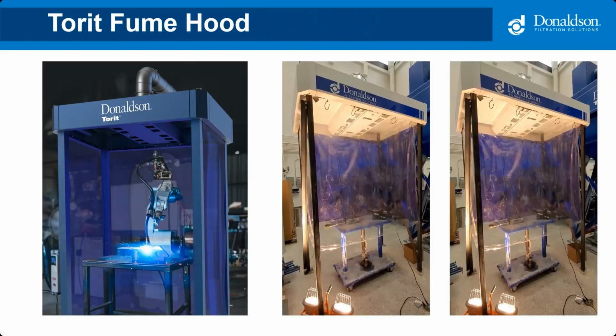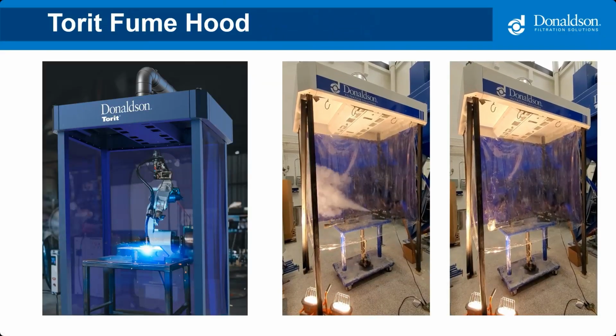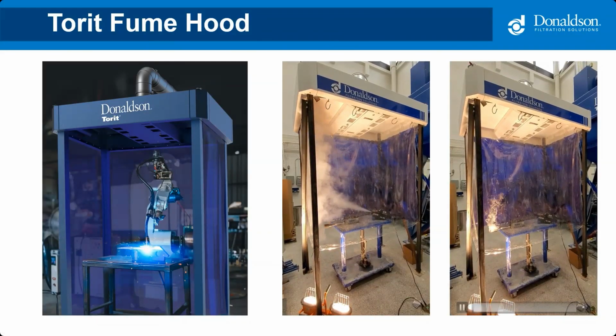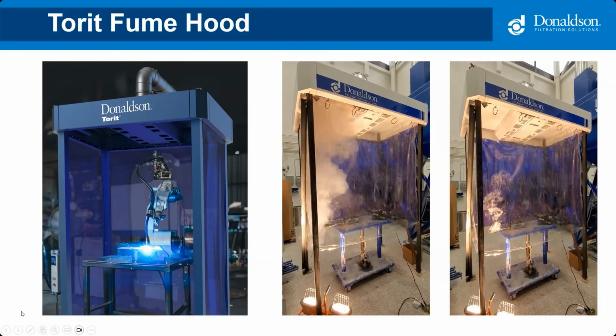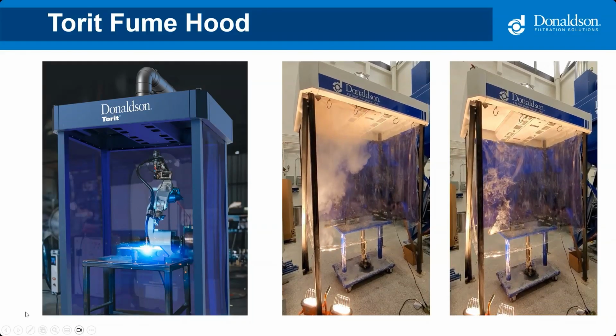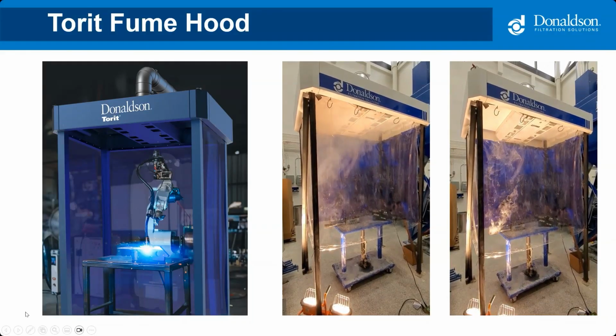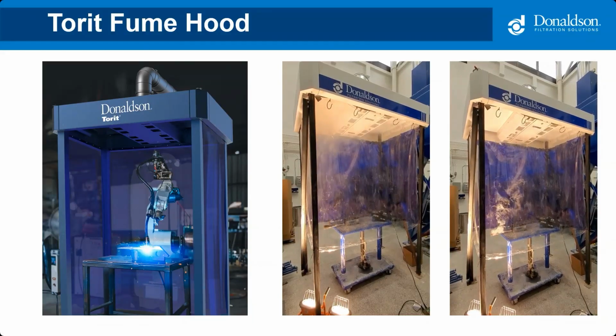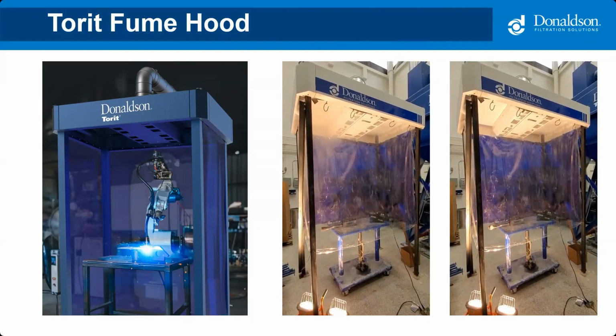Okay, for weld fume, you see there may be large hoods like this, often with curtains for welding stations. We do a lot of testing at Donaldson, so we thought it would be fun to show you a few testing videos of our fume hoods. The video in the middle, which you can see there is moving, is using a smoke machine with the hood being tested in the lab. This would simulate robotic welding. You can see that on the left. The video on the right is more realistic for manual welding, where small amounts of fumes are being emitted and cleared.